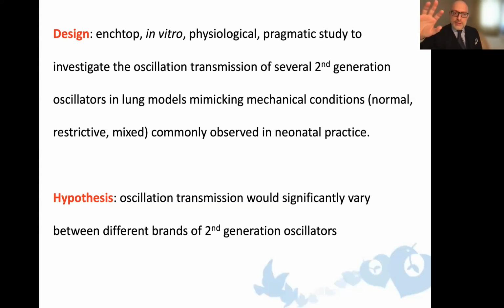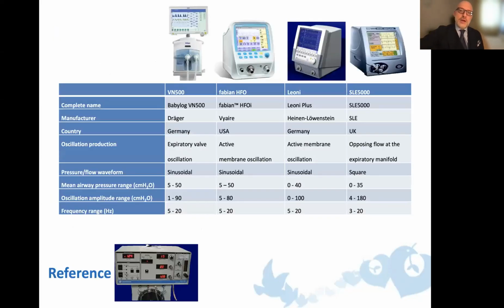So we focused on that, and we created a benchtop in vitro physiological model to study this on many second-generation oscillators. And the hypothesis was that the oscillation transmission would significantly vary between the different brands, but also according to the different lung mechanics conditions. So here you see we tested the VN500, the Fabian HFO, the Leoni Plus, and the SLE 5000. And you can clearly see that the technical characteristics are very much different. Even the oscillation amplitude ranges that the manufacturers claim to provide are widely variable. And then you will see in a second, the results are also widely variable, and these ranges are not actually achieved by the machines as the manufacturers tell us.